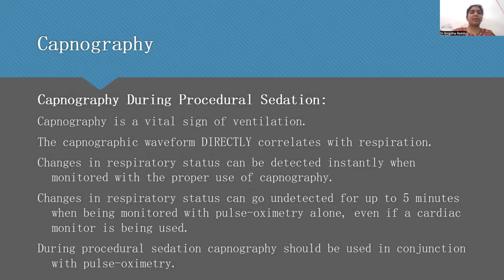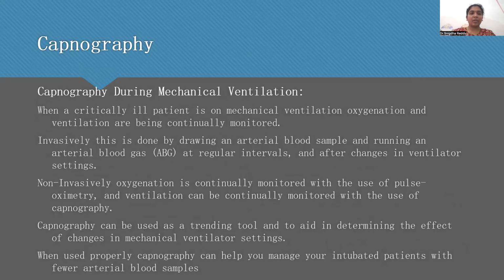Changes in the respiratory status can go undetected for up to 5 minutes when being monitored with pulse oximetry alone. But when capnography is used, immediate changes can be detected. During procedural sedation, capnography should be used in conjunction with pulse oximetry.